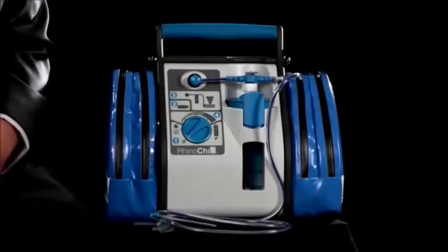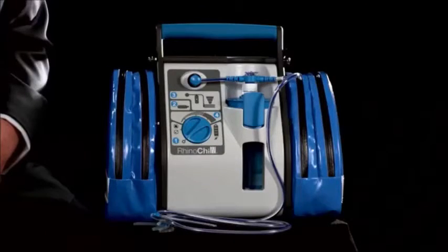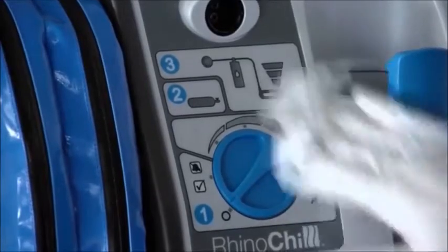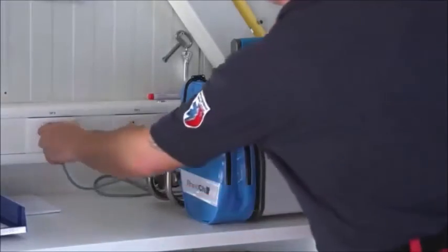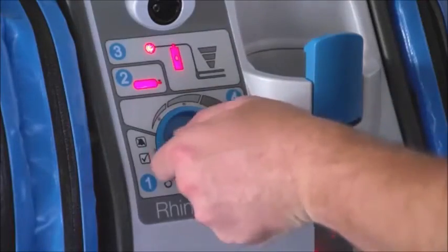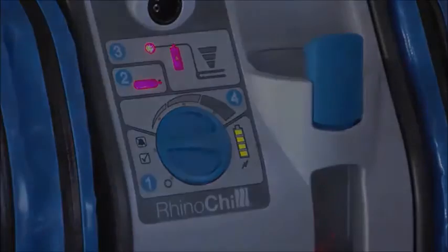Immediately following patient use, the exterior surface of the control unit and the accessory bags should be cleaned using a dampened cloth with warm water and a diluted, mild, non-abrasive, non-staining standard hospital disinfectant or detergent. Alternatively, seek advice from your department's infection prevention and control manager for the recommended solution for hard surfaces as used within your unit. When the device is not in use, ensure that it is connected to an external power supply to ensure continuous charging of the unit. At least once a week, the battery should be checked by unplugging the control unit from the external power supply and turning the control knob to the checked position.